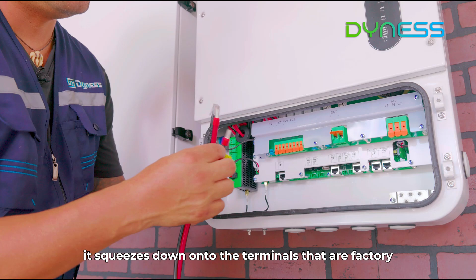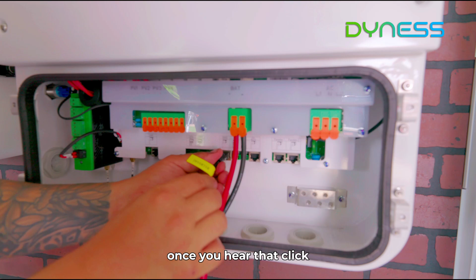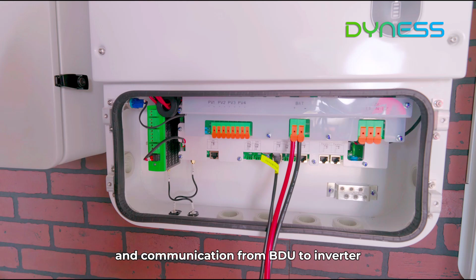And what you want to do, positive with the positive, negative with the negative, make sure they're completely installed firmly. Gently press down, negative, then the positive. Be sure to give a nice tug on each individual wire to make sure they are secured for the terminations. Then you want to take your communication from your BMS port. As you can see, there's only one orientation that needs to be installed. Once you hear that click, that communication is ready from BDU to inverter. And that'll complete the installation from positive and negative and communication from BDU to inverter.